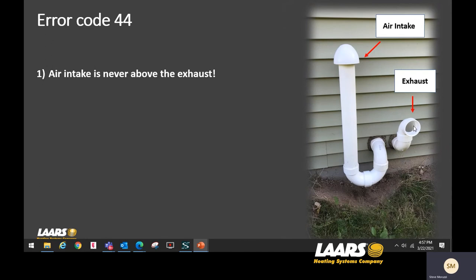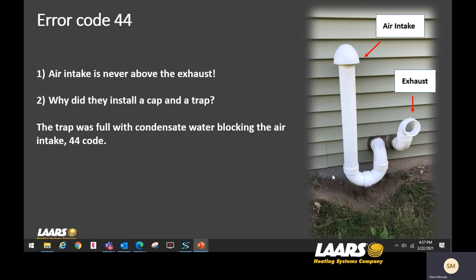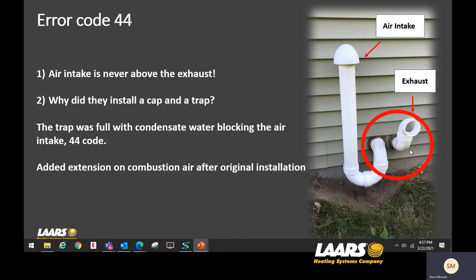Here's another job where again the exhaust was down and the combustion air up top — that's wrong. Why were there two 90-degree fittings creating a trap? That trap was getting full with condensate, blocking the combustion air intake and giving a 44 error code. During installation, the inspector noted they weren't 12 inches off the ground — you're supposed to be 12 inches above anticipated snow level. So they added two 90s, an extension piece, and a cap. Exhaust gases traveling up got drawn back in and condensed inside the pipe, filling it with water and giving a 44 error code. Inspect the vents.